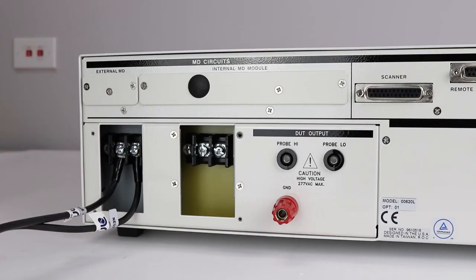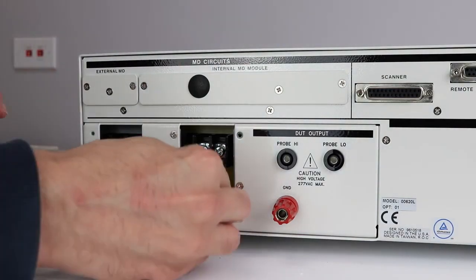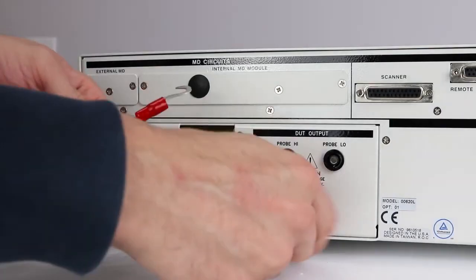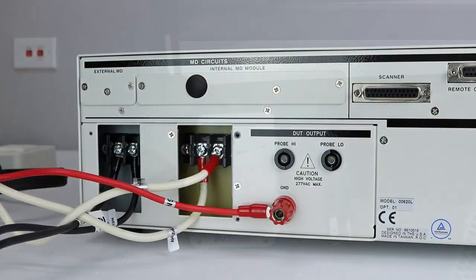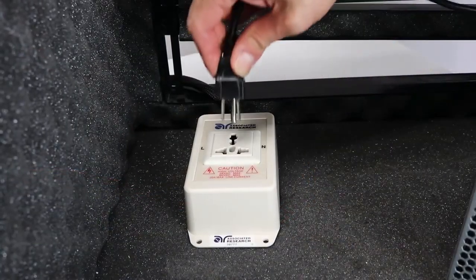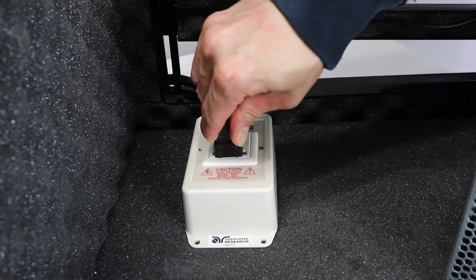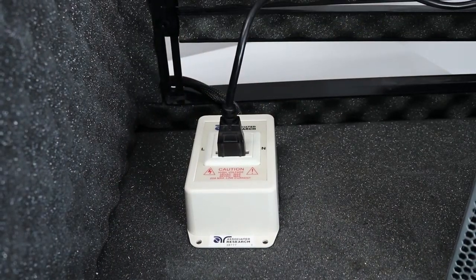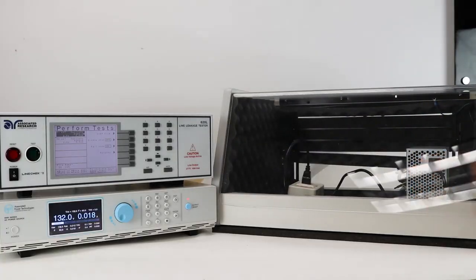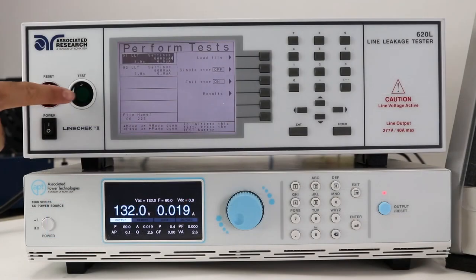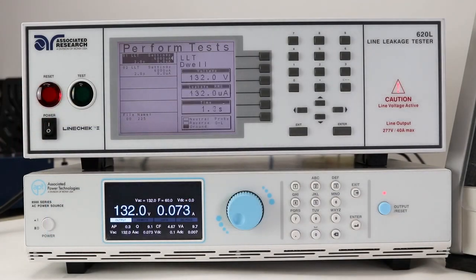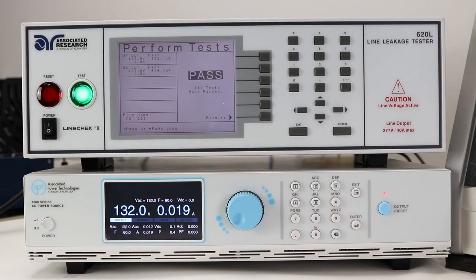Next, we're going to connect to the adapter box. These connections provide power to the DUT during a line leakage test. Connect the adapter box to the line, neutral, and ground terminals on the rear panel of the LINECHEK. To connect the DUT to the LINECHEK, simply plug in the Class 1 DUT into the adapter box. Close the DUT enclosure door and stand back. Push the test button to run your test sequence. Once your test sequence has completed, use the arrow keys to review your results.